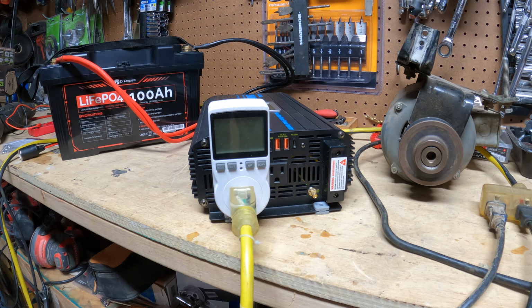So I'm going to apply loads that are common. I'm going to do a series of power tools, a small inductive motor, a heat gun, shop vac, just to see what it can do. It says it can do 100 amps continuous, so we're going to see if it can do that and stay there for a few minutes. And then we're also going to see if a big load comes on, if the internal BMS shuts it down to keep it safe.